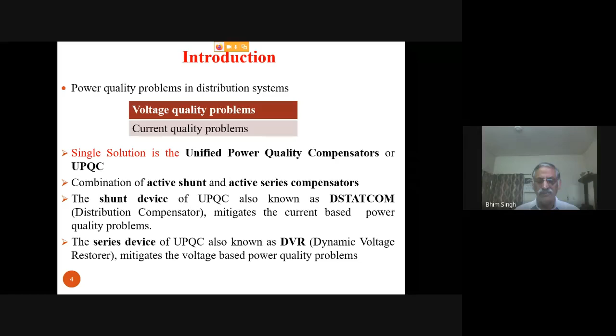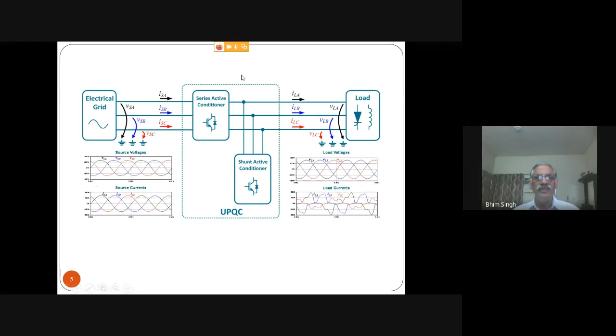In many situations, like for a distribution company or custom power devices, you may not have harmonics, but these requirements may still exist because of voltage fluctuations or voltage unbalance in three phase, or current unbalance in single or three phase. So think of the UPQC device: you have a series conditioner and a shunt conditioner. The voltage here may be distorted or unbalanced, but your load is ready to accept only sinusoidal and balanced voltage. Your load current may be non-linear and distorted with reactive power, but you want the supply current to be sinusoidal.